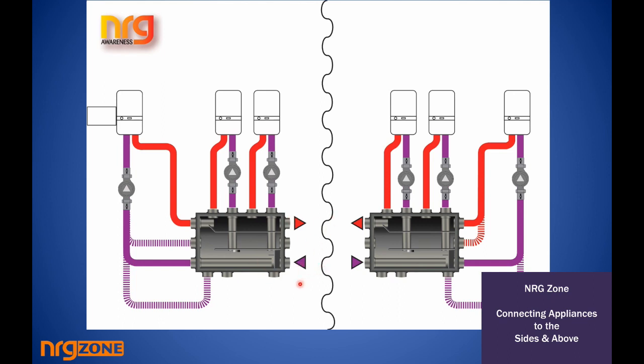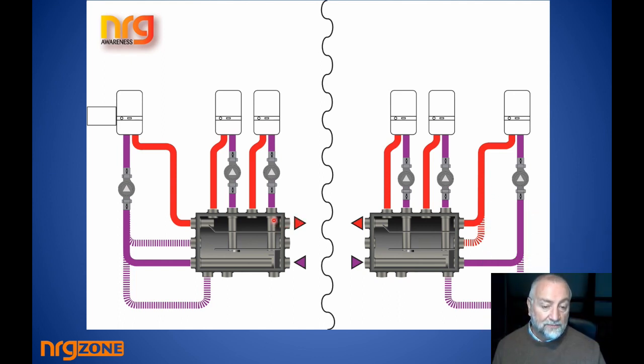off to our zones. Another trick is that if you had inch connections here, there's utterly no reason why you couldn't go, say, with an inch by inch and a half or inch by inch and a quarter iron nipple threaded into here, and go immediately to a bigger pipe size, because the resistance over these sockets is not worth talking about. So you can take a much bigger volume of water away even from a standard unit without having to go to a bigger size unit. You'll actually find it would be cheaper to go to the bigger unit with regard to socket sizes, because it costs more for the fittings and the labour than it does to just get the bigger unit. So we do make units that have bigger connections on the side.